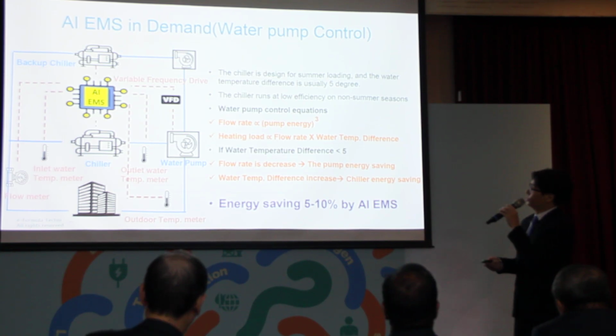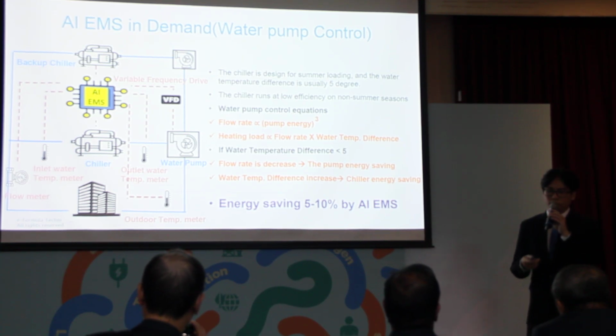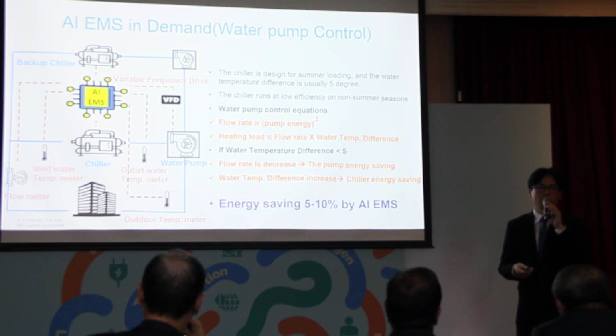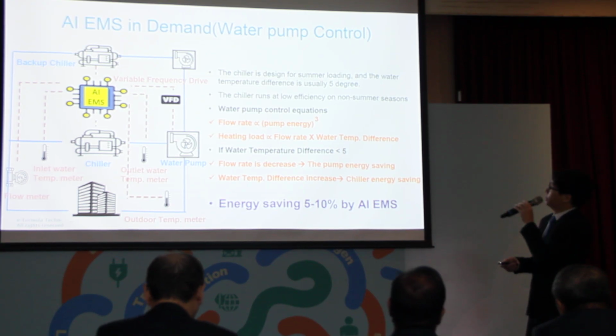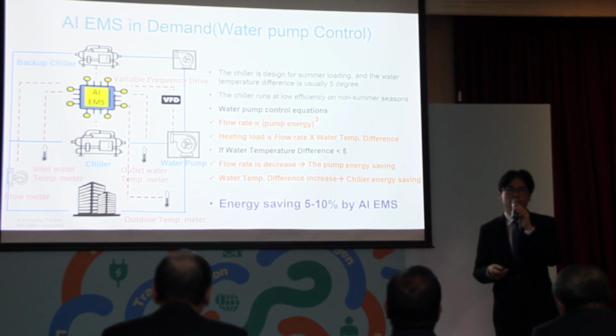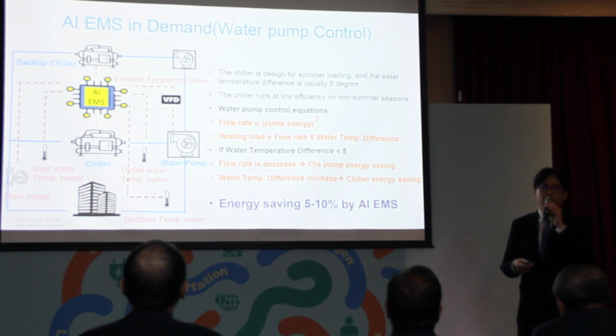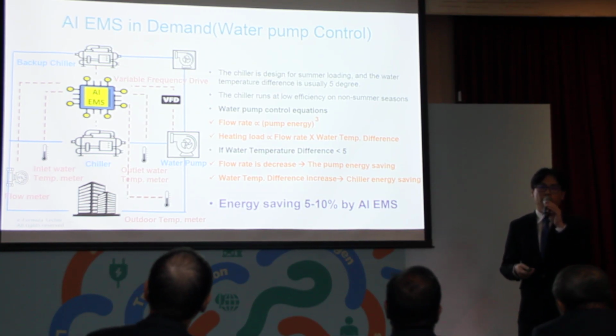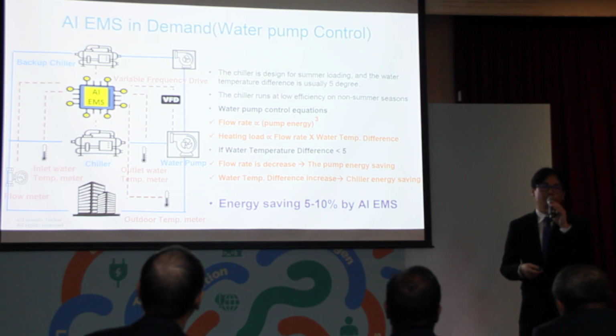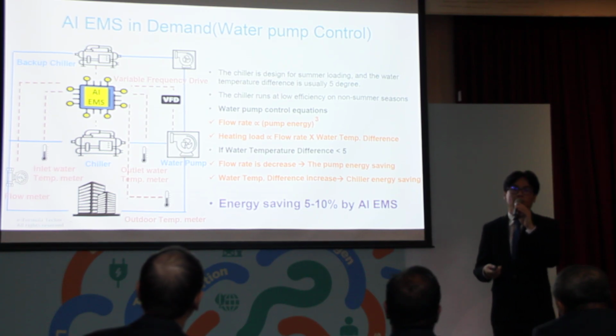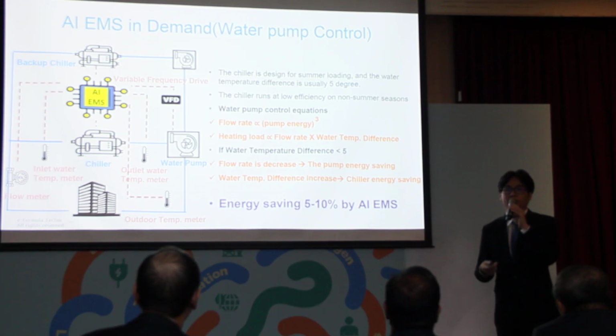According to water pump control, there are two major equations we must know. The first is that the pumping energy consumption is proportional to the flow rate cubed. So if we reduce the flow rate, we can get very high energy savings from the pumping power. For example, if we reduce the flow rate by 10%, we can get about 27% energy savings from the pumping power.